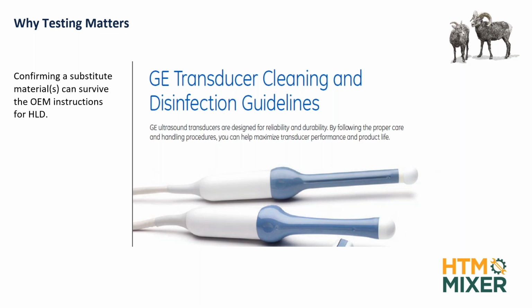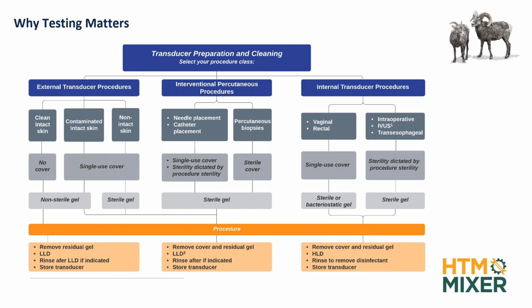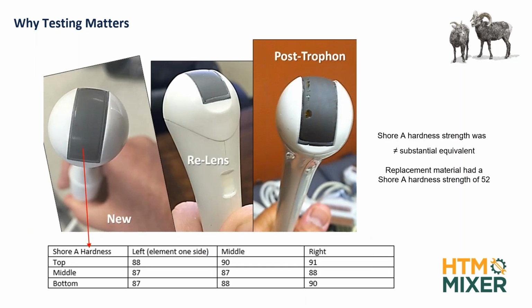So these are the disinfection guidelines, and we've noticed that people don't check that. That's another thing. If you're going to replace the insertion component, the handle component, the dome, and you're going to use a material that has non-deterministic characteristics because you didn't do the testing, you don't know if it'll survive the cleaning or high-level disinfection, right? And this is from the AIUM, and every protocol is outlined for these things, very tightly controlled, especially for intracavitary probes. As you can imagine, surgical probes sometimes have to be sterilized even. And so this contributes to the life and early death of the probe if they aren't followed. Here's a new one. I don't usually call out companies, but I'll just use its initials, Trophon.